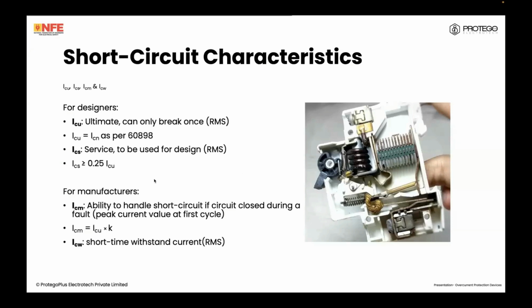Manufacturers will also give us an ICM and what's called an ICW. An ICM is the peak current value in the first half cycle of the wave during a short circuit. If the circuit is completed during that time, the OCPD has to handle that peak current value. This is what the ICM value is. This is for a circuit breaker really. This is really only for the manufacturer. For the designer, the earlier values are applicable. For the manufacturer, these values are applicable.